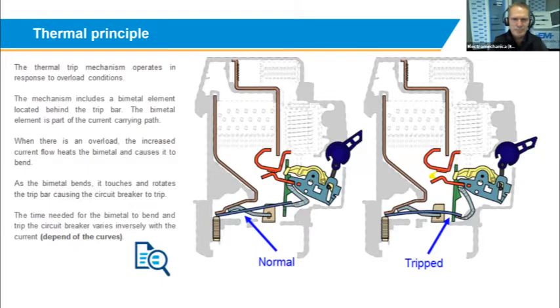Then to get to the explanation, or try and explain to you what the thermal principle is that we talk about. When we talk about miniature circuit breakers, we normally say that it's a thermal magnetic product. So what does the thermal mean, and what does the magnetic mean? The thermal part is your overcurrent technology that they use inside the product. They use a bimetal strip, so it's two different metals that they put on top of one another, and then the current flows through it. The higher the current flow, obviously the more heat is generated, and this heat then bends the bimetal strip inside the product. Then eventually, when it reaches a certain current or temperature, it will trip the product, and your product will open safely.